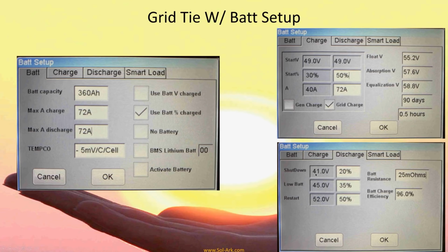So what this is doing is this says I will indicate a low battery at 35% SOC, and the battery icon turns yellow. Then it'll shut down the inverter, but keep the PV charge circuits on at 20% full. And once the batteries get back up to 50%, it will restart the inverter output. This says, can you equalize over 60 volts for a flooded battery? We cannot. For some of the flooded batteries, you might need an external equalizer to do some of that.